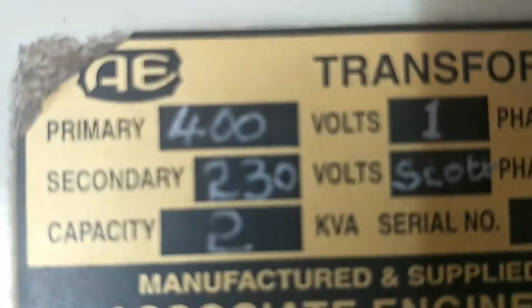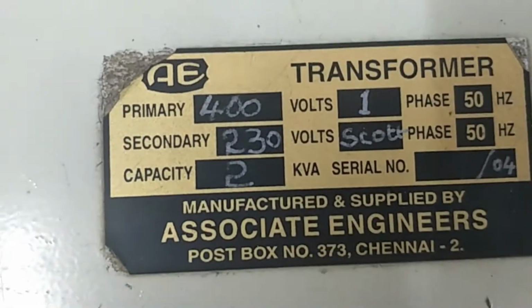Coming to the nameplate details, it is already mentioned here. The capacity of the transformer is 2 kVA. The primary voltage is 400 volts and the secondary side is 230 volts. Is it clear? Inside this you are going to consider two transformers, and that is the rating for each transformer.